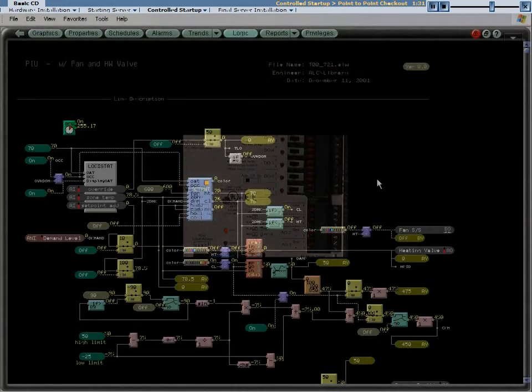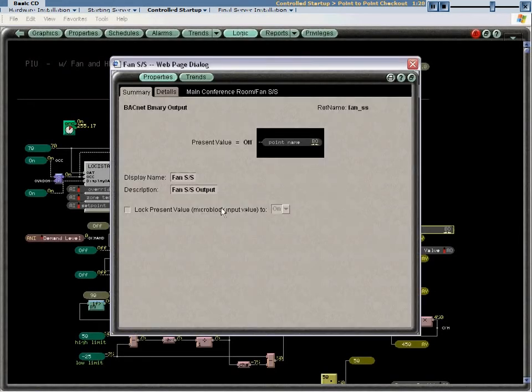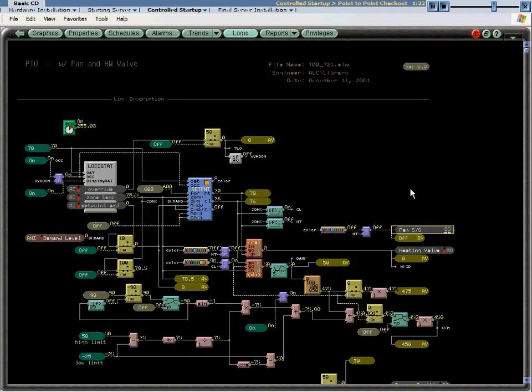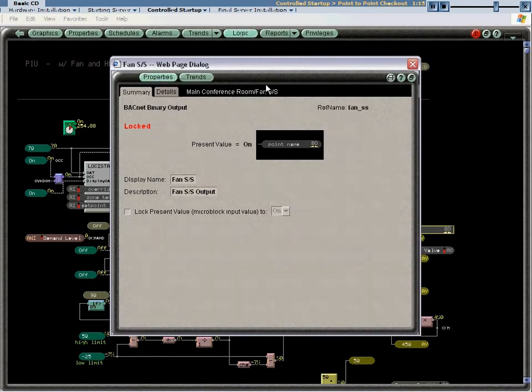Now, on the control module, set the binary output's HOA switch to automatic. Lock the binary output point on from the logic page. Then verify the device has turned on. Next, unlock the binary output point. And then finally, on the control module, set the binary output's HOA switch to off. Note: if the lock conditions on the properties page are reversed from actual conditions, the polarity, normally closed, normally open contact position, is set incorrectly. Change the polarity and check the point again.